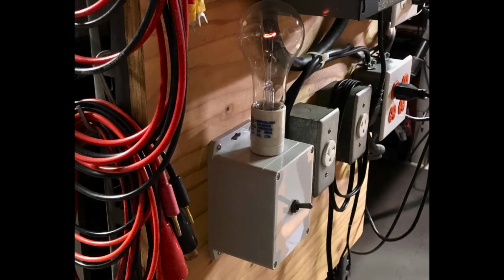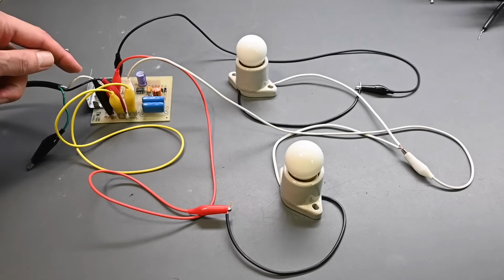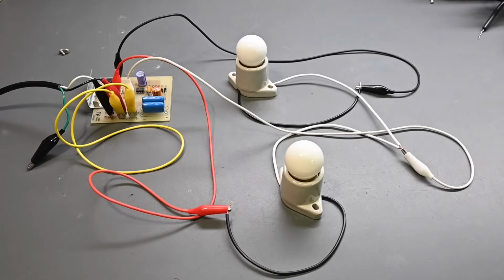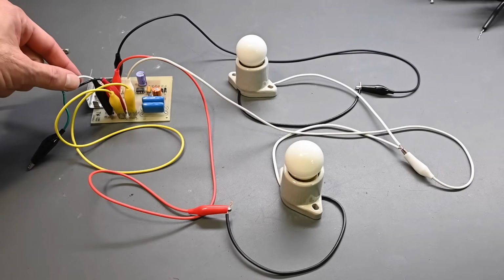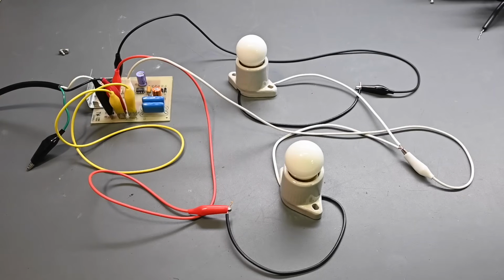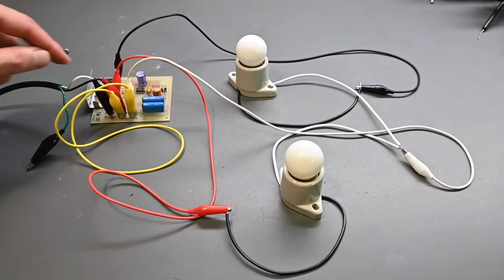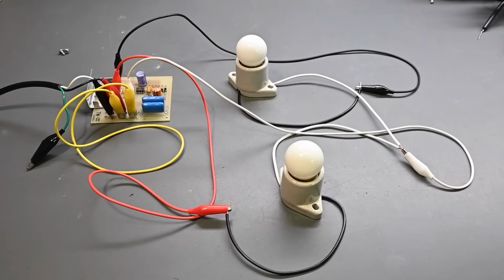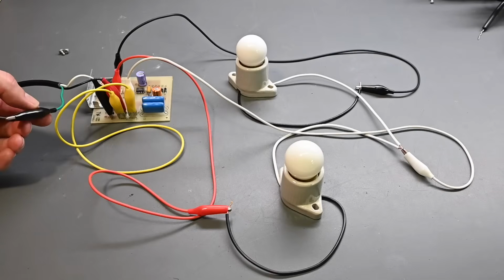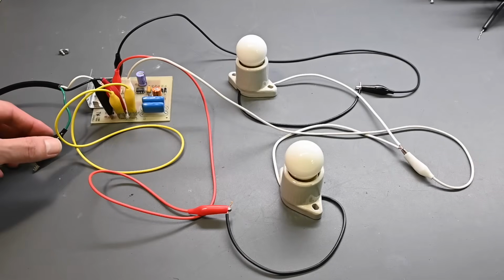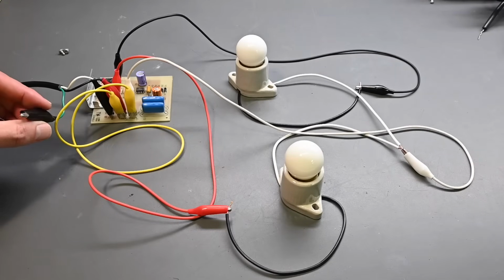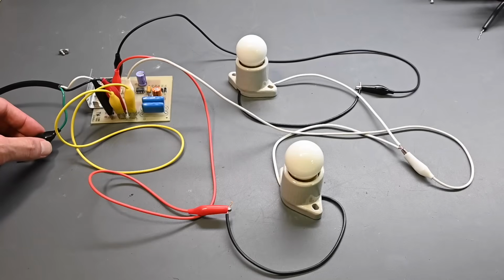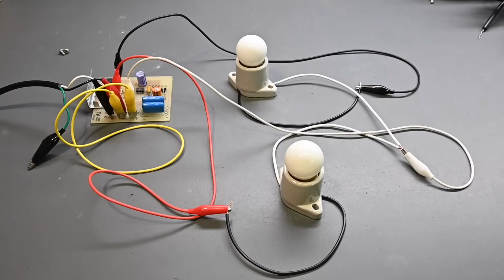Please remember that the voltage across this AC line, even though it's off the isolation transformer, is still lethal. You would get a very serious, if not lethal, shock across this AC line. The purpose of the isolation transformer is to protect from shock from the AC line to ground, because there's no earth-ground reference on the secondary of that isolation transformer. This ground wire is not connected. It's a 3-wire cord, but on the isolation transformer there is no ground, and the ground connection in the outlet doesn't go anywhere, so it's left disconnected.